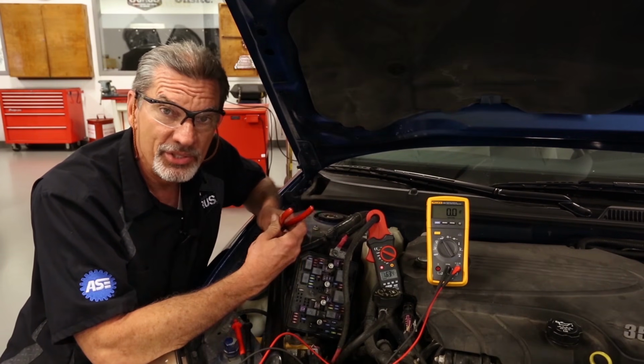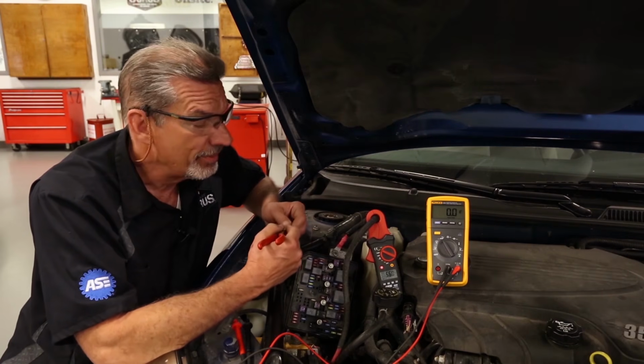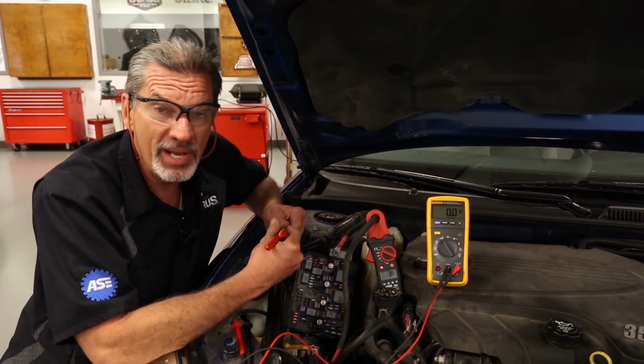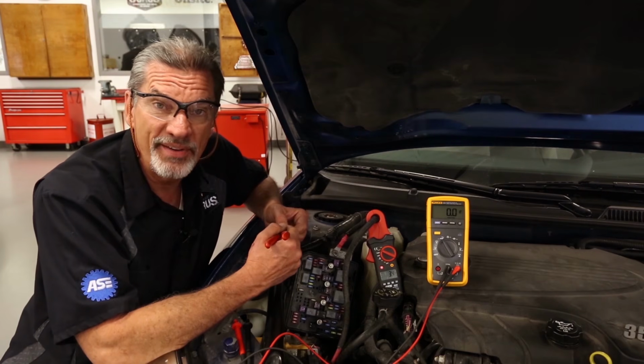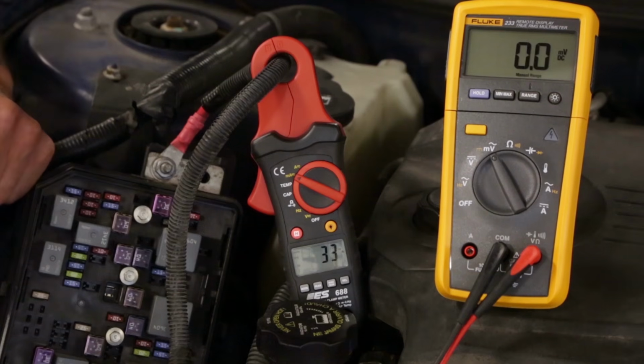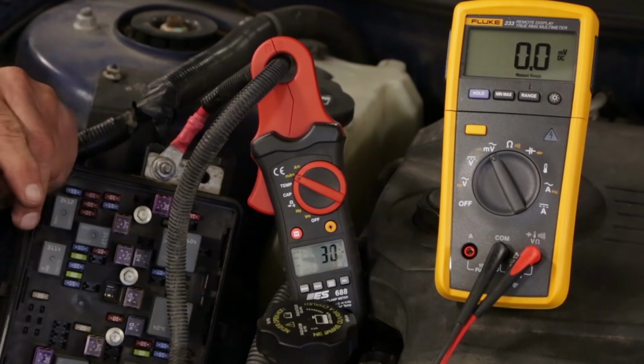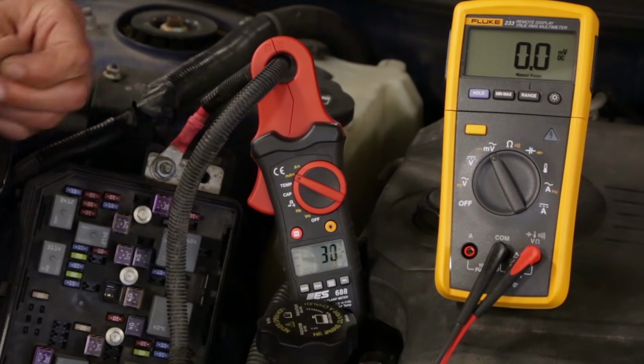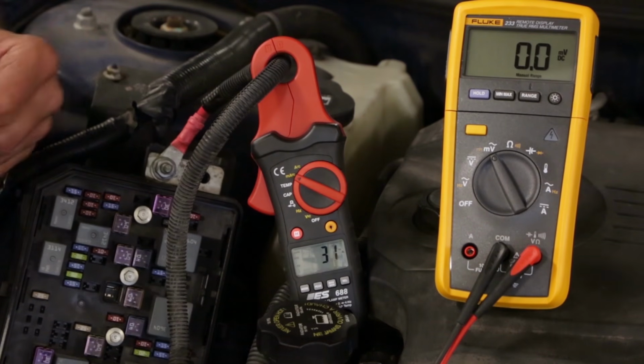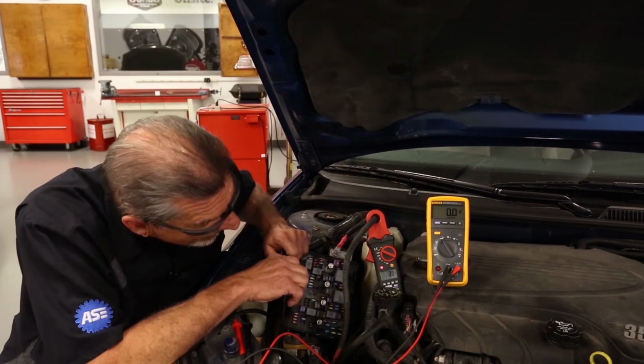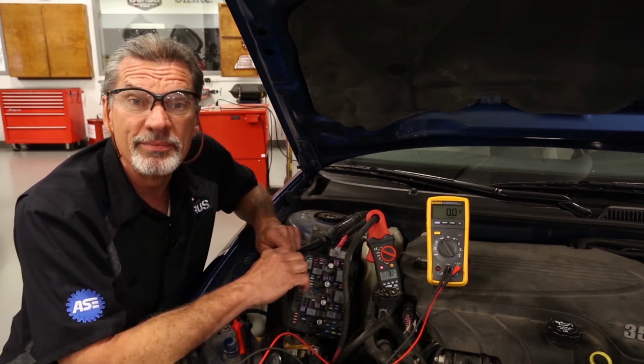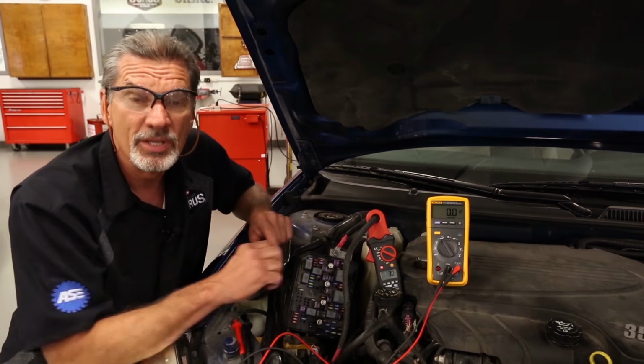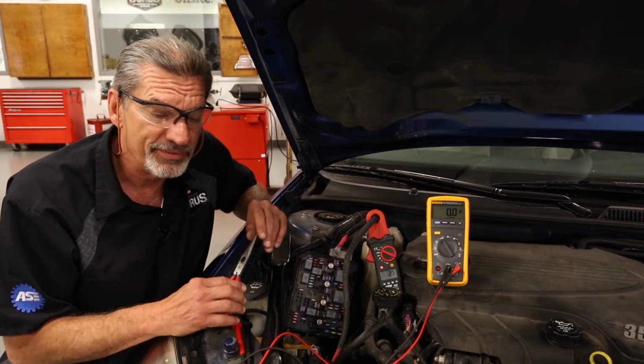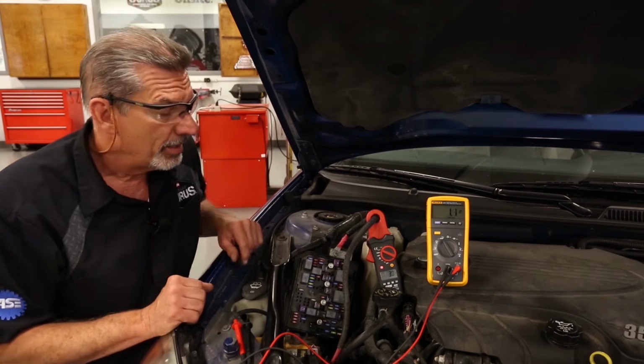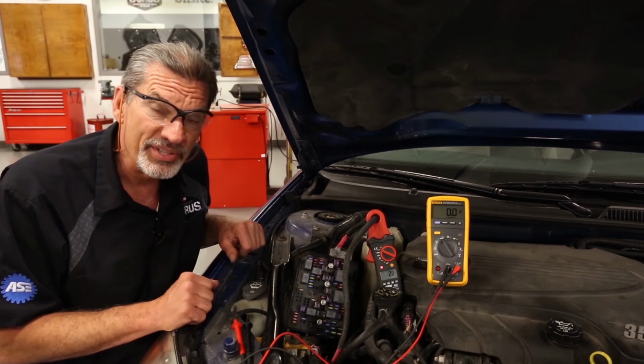If you wait a while, sometimes the current will drop down fairly quickly. Sometimes it may take as long as 45 minutes to an hour. So as we watch this, well, there it's back down to 32 milliamps already. So it's almost within spec. If we give it enough time, it should drop on down to be within specification again. But that's one of the issues you run into pulling fuses. If I did have a large draw in the system, there's another technique we can use.